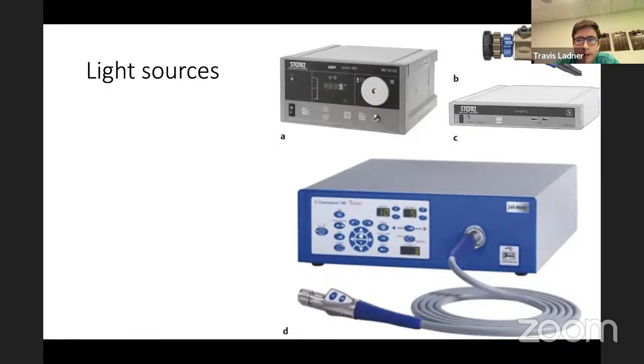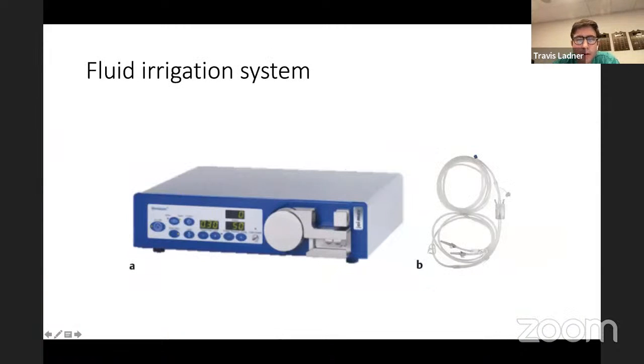You can hook up to whatever type of light source the hospital has. For instance, at Sinai, we have the Storz Towers, and it integrates well with that. The irrigating ports on the endoscope, you can hook up to continuous fluid irrigation. And this is very important for the operation. One, because it continuously irrigates any debris and blood that's encountered during surgery. It also has a tamponade effect, so you can irrigate and occlude the outflow from the endoscope so that you can create some back pressure.